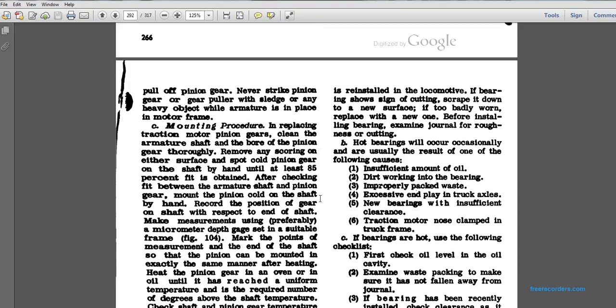Mounting procedure. In replacing traction motor pinion gears, clean the armature shaft and the bore of the pinion gear. Thoroughly fit the pinion gear cold on the shaft by hand, spotting the surface, until at least 85% contact is obtained. After checking the fit between the armature shaft and pinion gear, mount the pinion cold on the shaft by hand. Record the position of the gear on the shaft with respect to the end of the shaft. Make the measurements using preferably a micro depth gauge and a suitable frame, figure 104. Make the point measurements at the end of the shaft so that the pinion can be mounted in exactly the same position after heating.